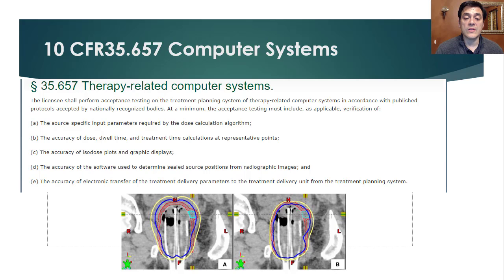The accuracy of isodose plots and graphic displays need to be checked. And the accuracy of the software used to determine sealed source positions from radiographic images, as well as the accuracy of the electronic transfer of the treatment delivery parameters. So every part of the process that goes from when the physician generates his prescription to the end part of the delivery needs to go through a quality check to assure that it's accurate. So the end-to-end test, as it's sometimes called, is a great check to make sure that we have everything in place as is mandated.